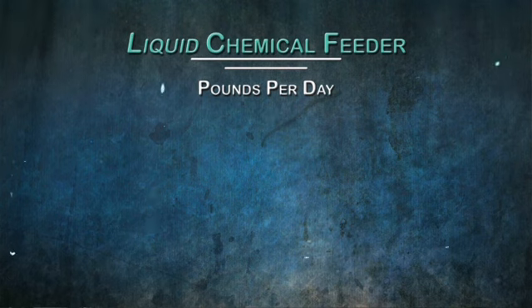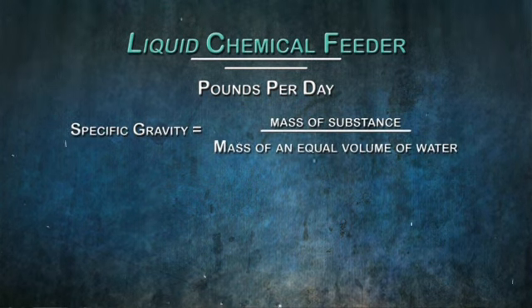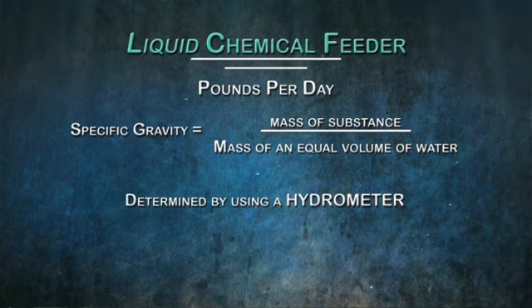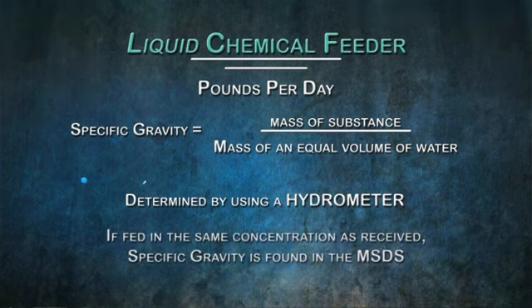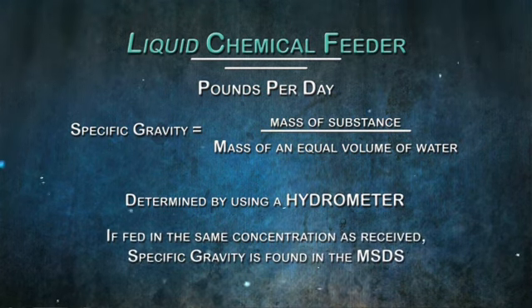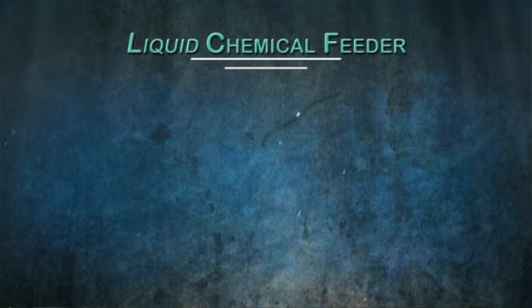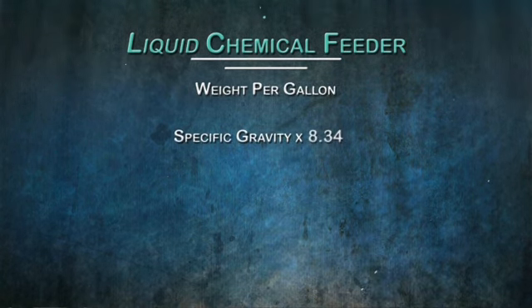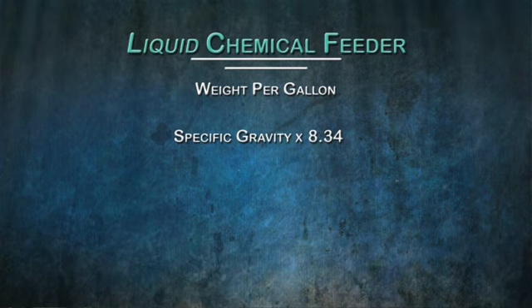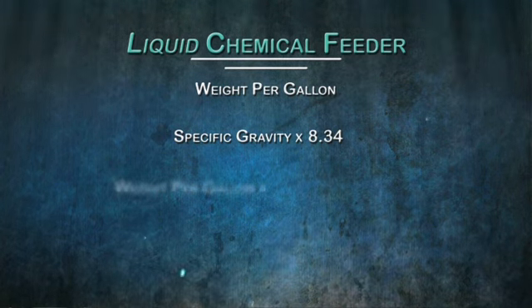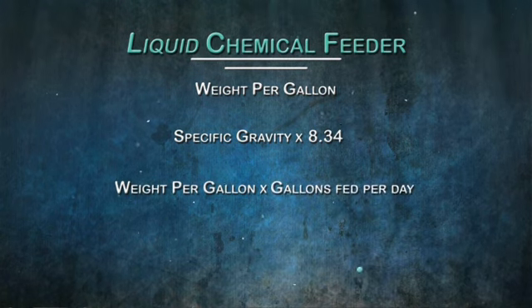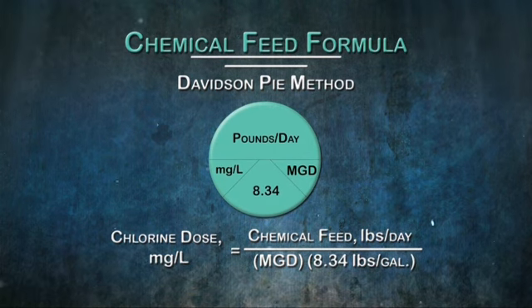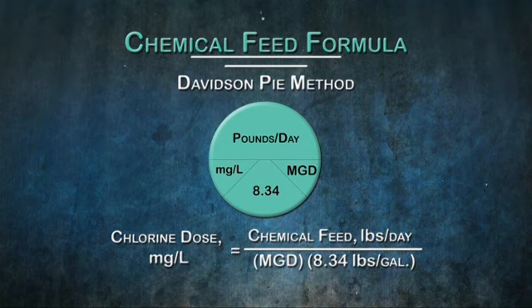Pounds per day is determined first by knowing the specific gravity of the chemical solution. Specific gravity can be determined by using a hydrometer. Or if the chemical is fed in the same concentration as received from the supplier, the specific gravity can be found in the material safety data sheet. The weight per gallon of chemical is determined by multiplying the specific gravity by 8.34. Finally, to determine the quantity of chemical solution being fed, you would multiply the weight per gallon by the gallons fed per day. Once you know the pounds per day feed rate, you can determine the dose concentration in milligrams per liter by using the Davidson pie chart.